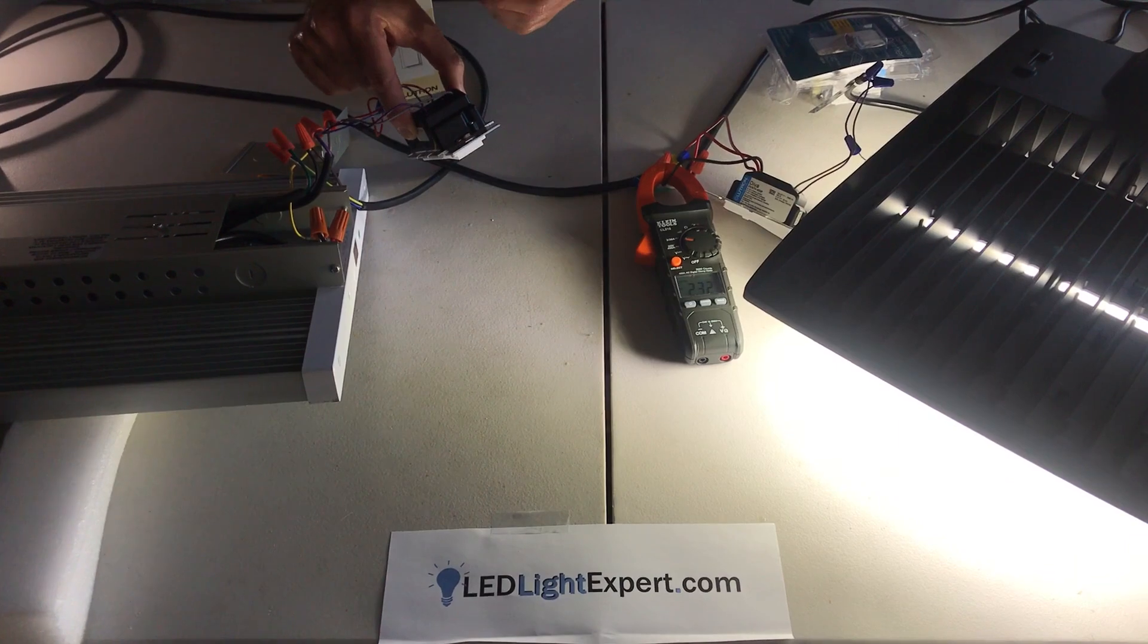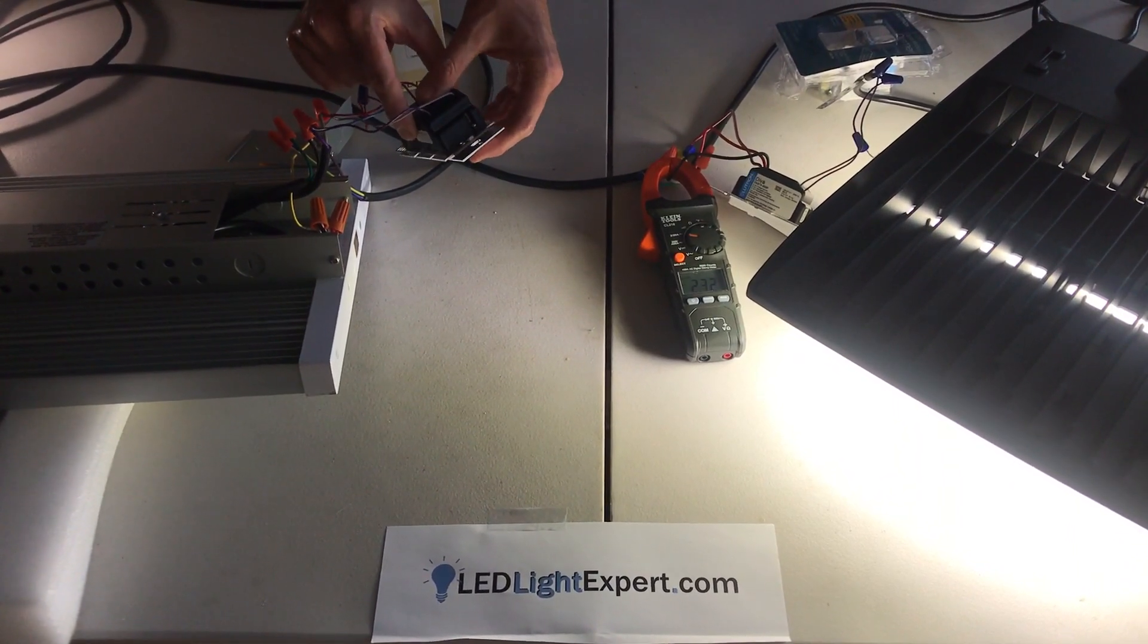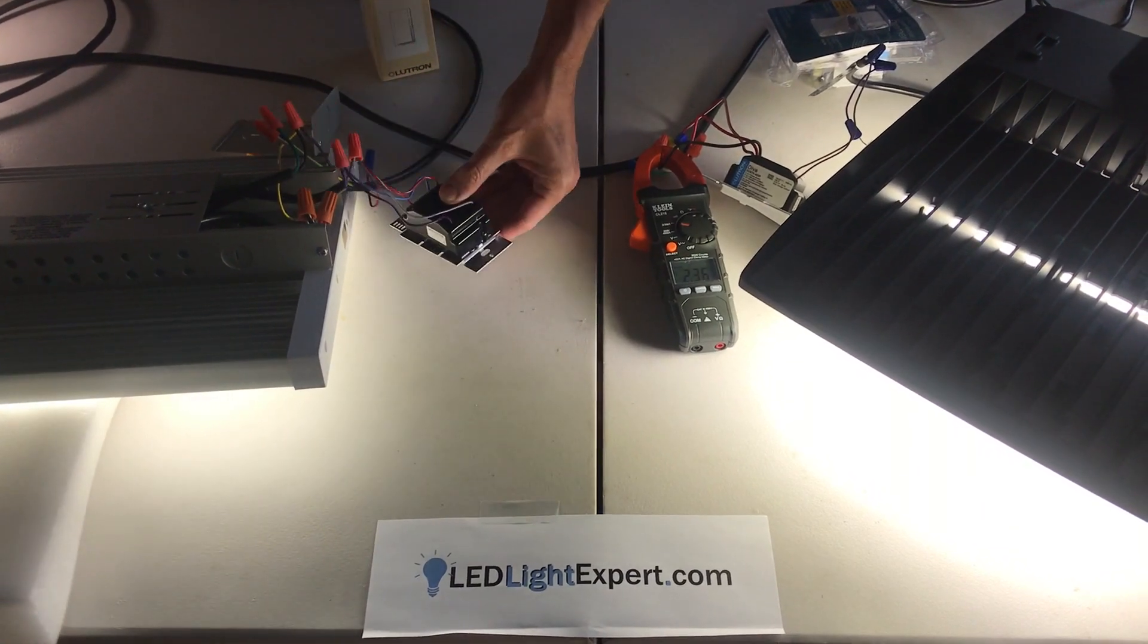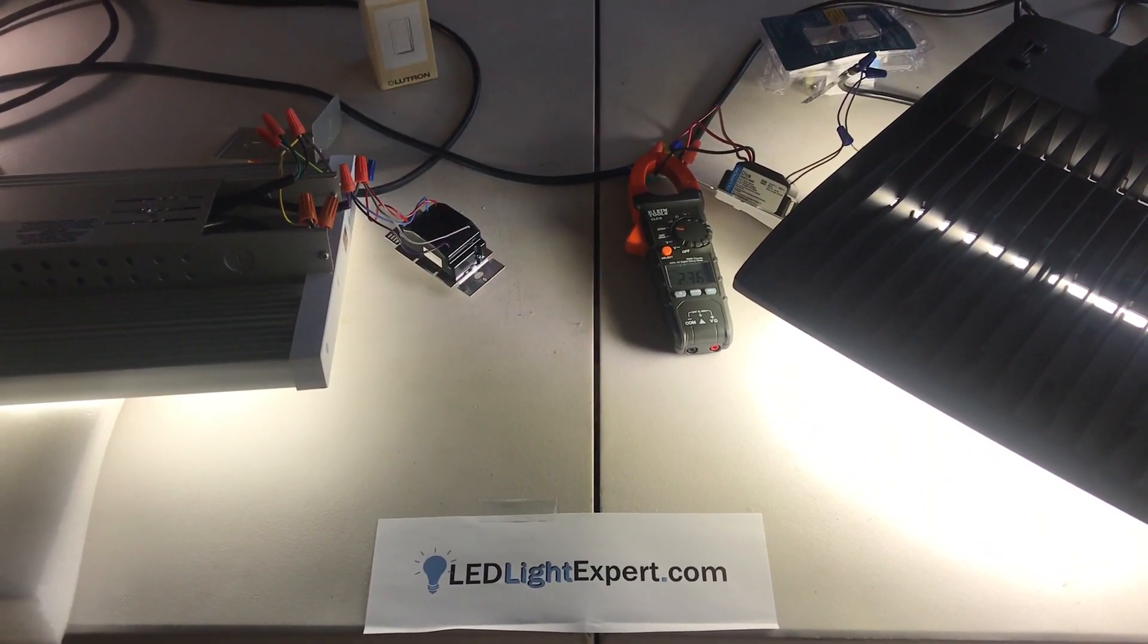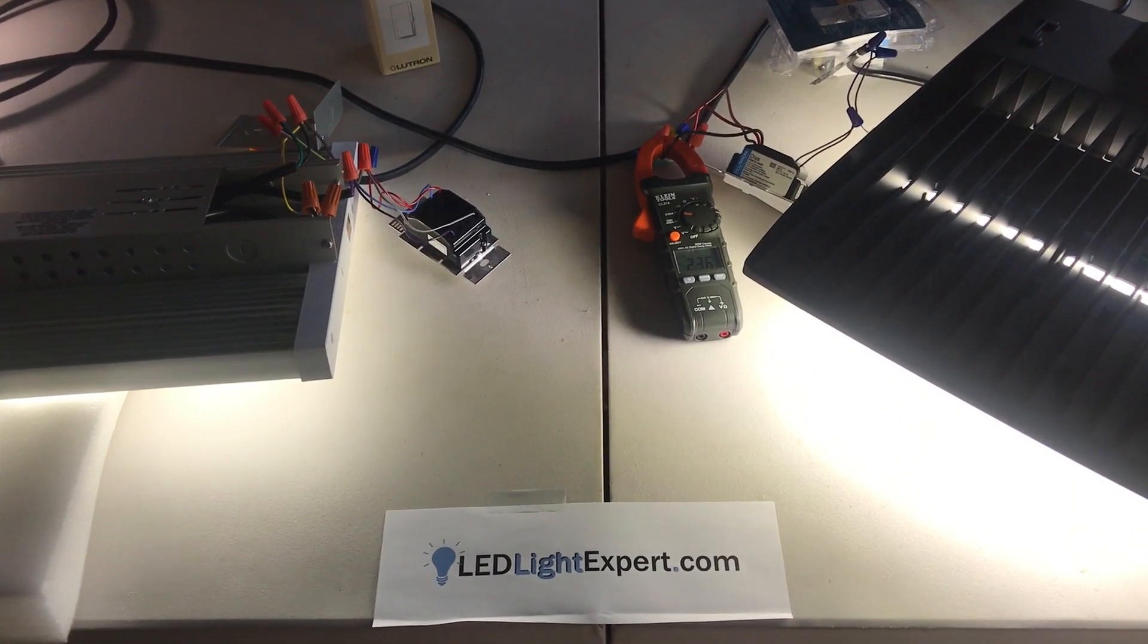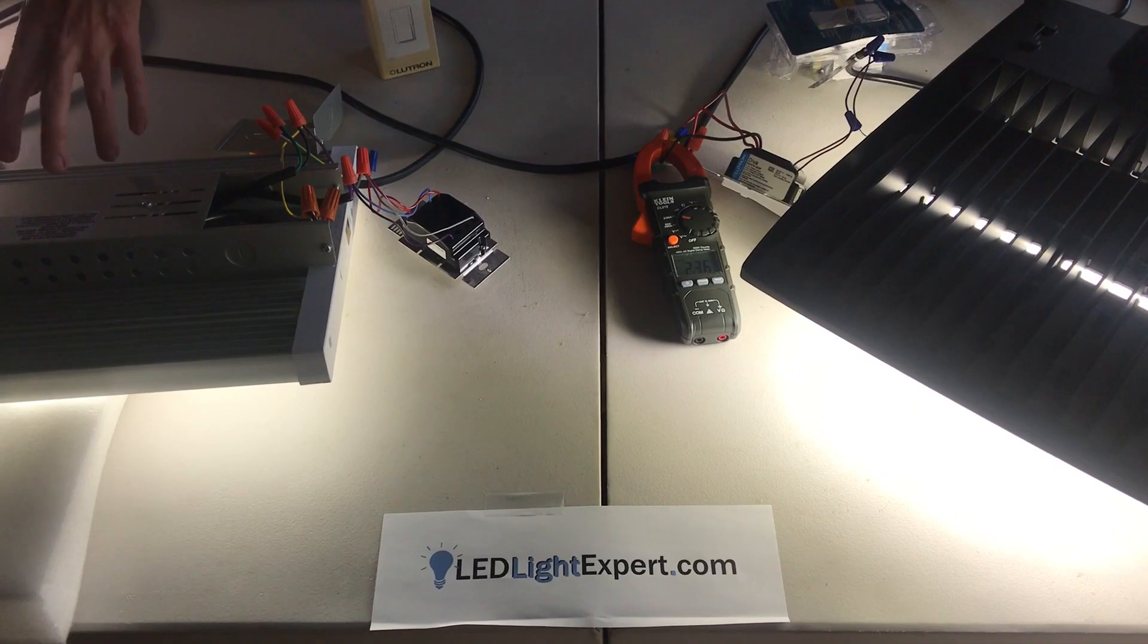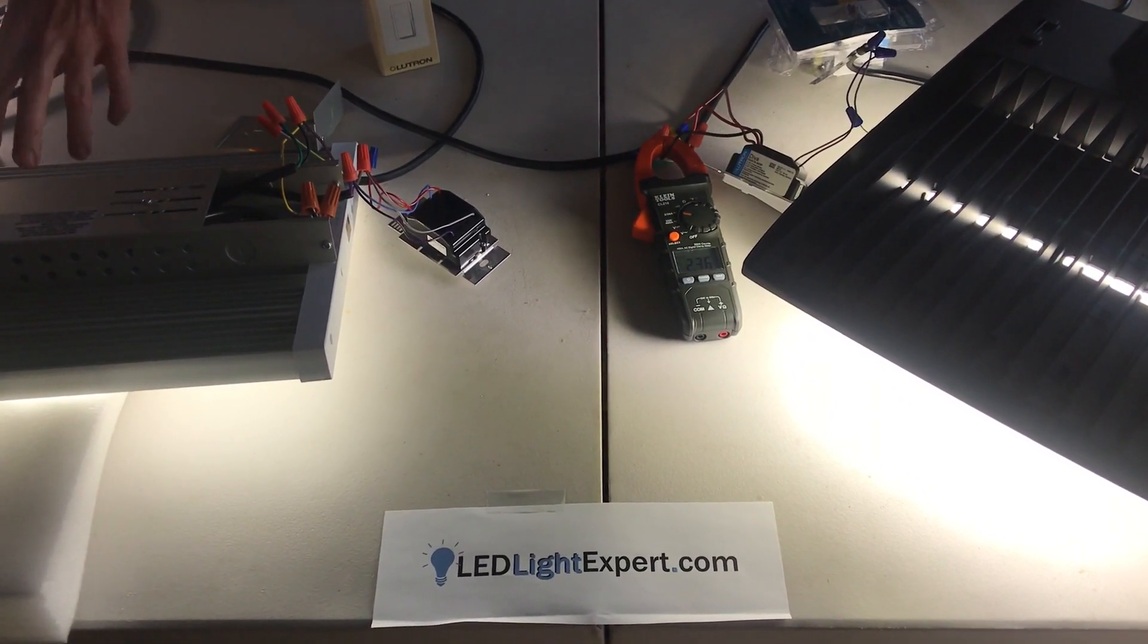It seems great, but unfortunately in practice this doesn't work all that well. The reason for that is a couple fold. Number one, there is no standard spec on this, so you get some incompatibility issues. The other reason is that all the driver makers are now switching from 0 to 10 volt to 1 to 10 volt.